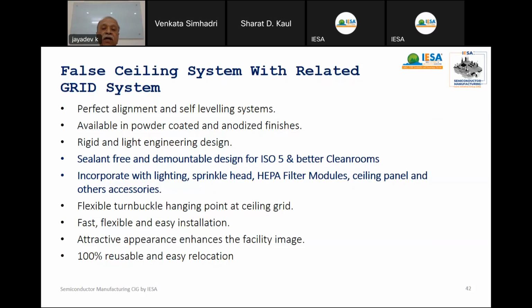It requires a special false ceiling. So perfect alignment should be there with self leveling systems. Available in powder coated and heat and light engineering. Sealant free and demountable type for ISO 5 and better. And it should be able to incorporate lighting, sprinkler heads, HEPA filters, ceiling panels, and other accessories. So they should be flexible, able to adjust the height, and it should be usable 100% after some time.